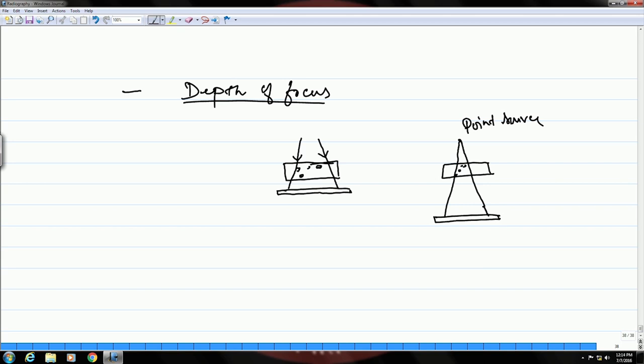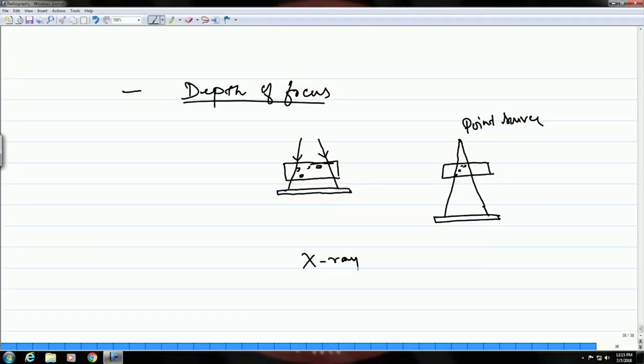A point source or micro-focus source provides better depth of focus compared to a finite size source. When the image is magnified using a point source, the other name for that is X-ray microscopy, because magnification is a key feature of microscopy. Just as optical microscopes use lenses to magnify, here the point source allows magnification of the X-ray image. This is how the size of the focal spot controls the quality of the image.